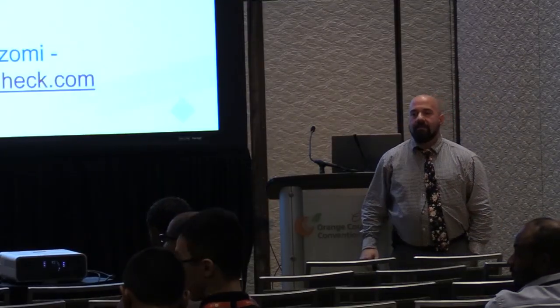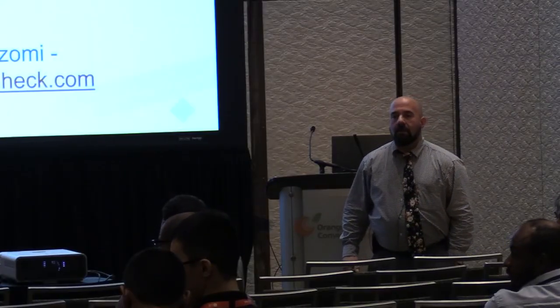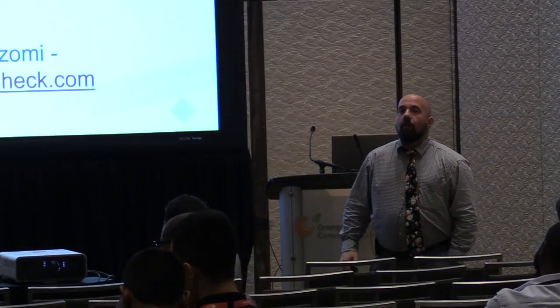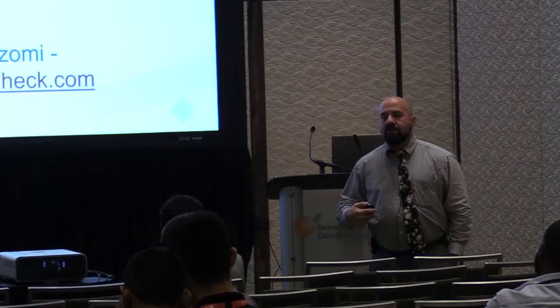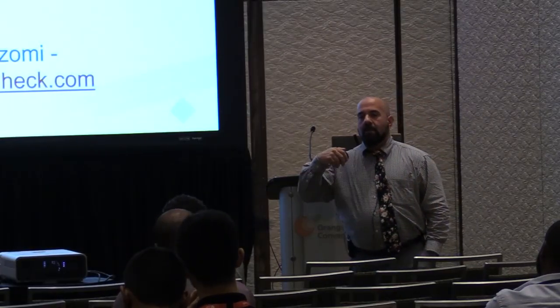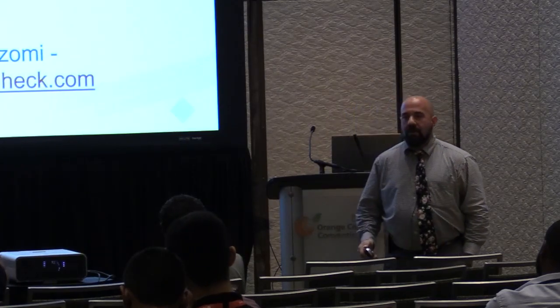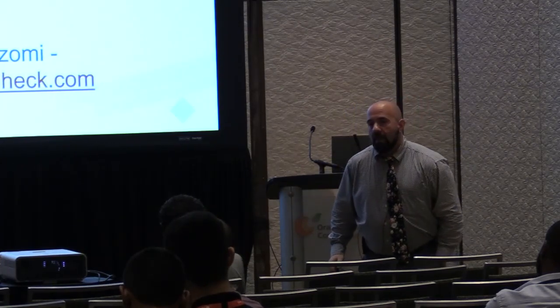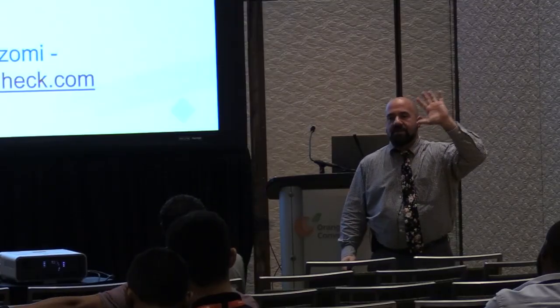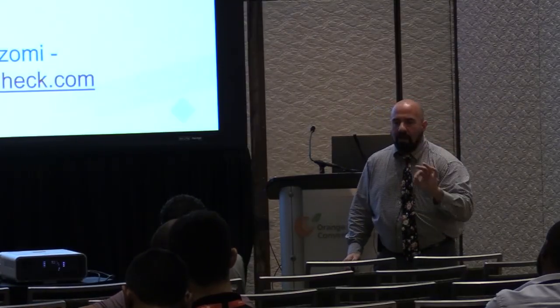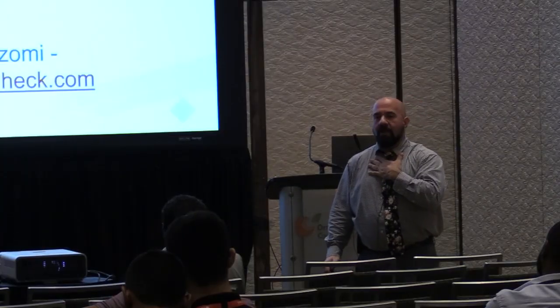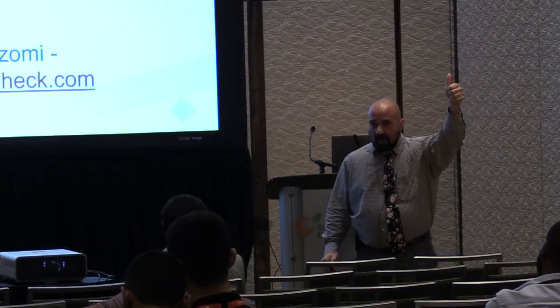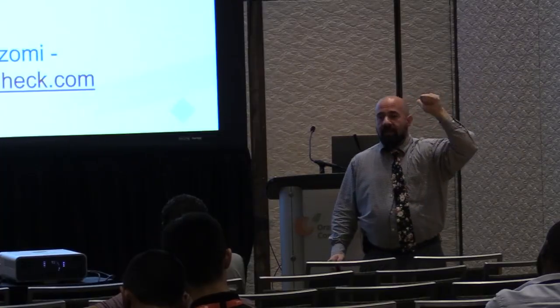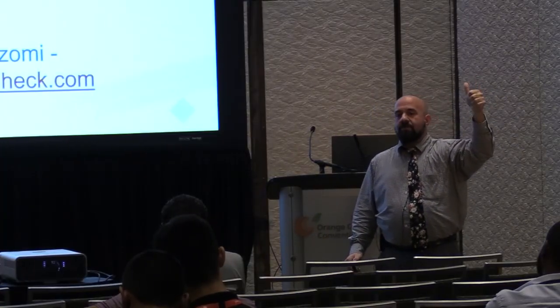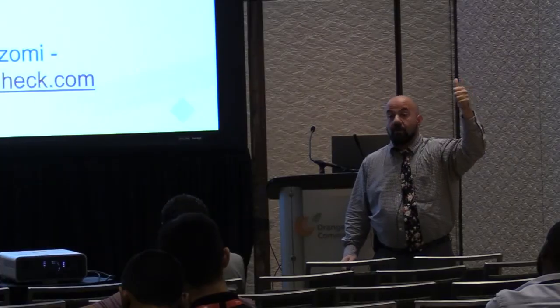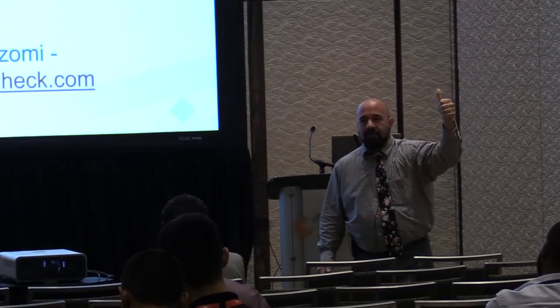Yes, sir. Who typically provides the smoke detector for a smoke damper? We have options as damper manufacturers to provide them as a factory-mounted and wired option. We don't like to do that. Our smoke detectors are usually a single type. The biggest problem with the smoke detectors offered by damper manufacturers is they are non-addressable. You have a smoke control system, you have a building management system, and they're non-addressable. So now we have to add addressable components to read them, or they create problems and conflicts.